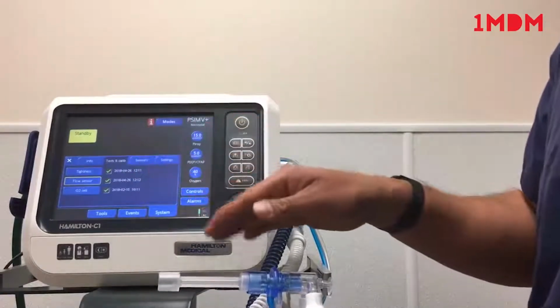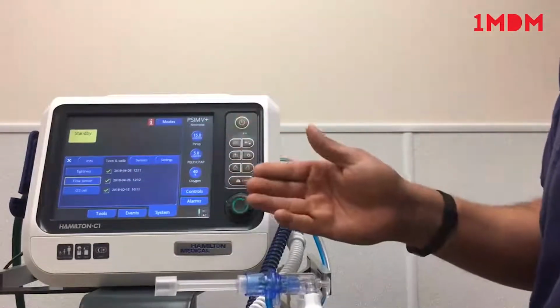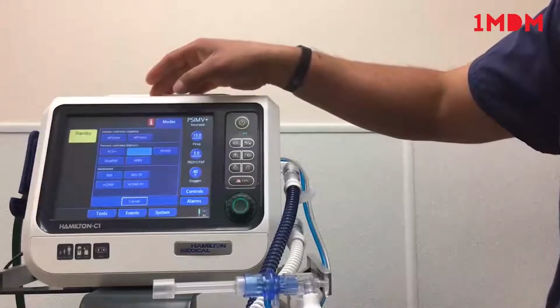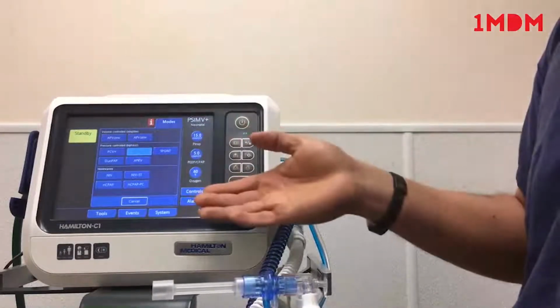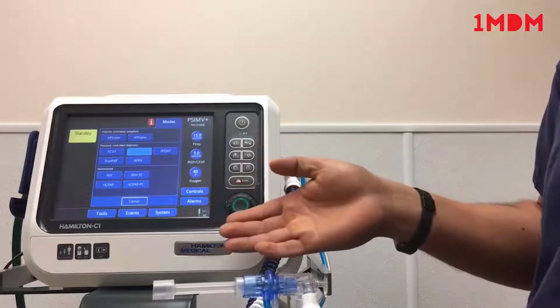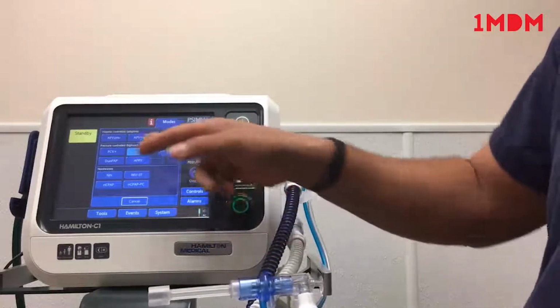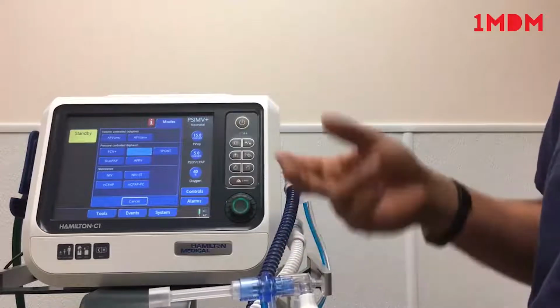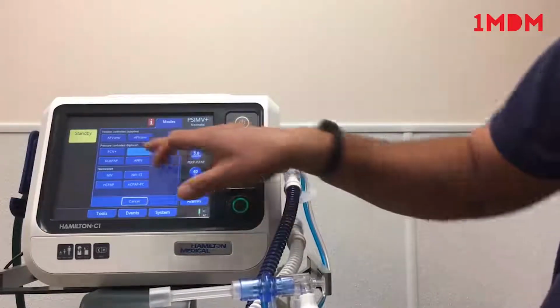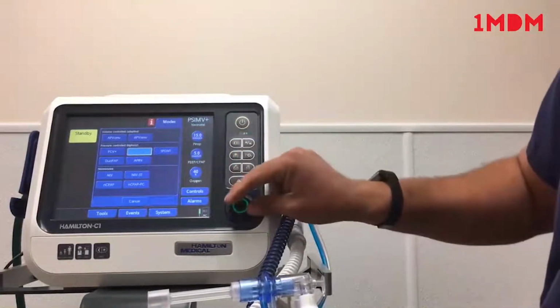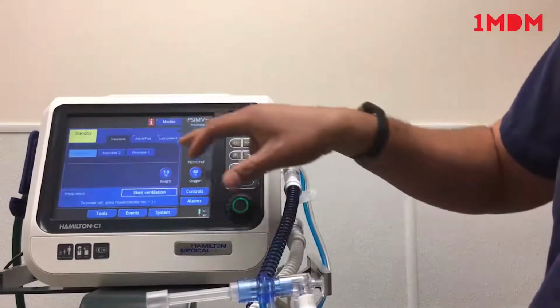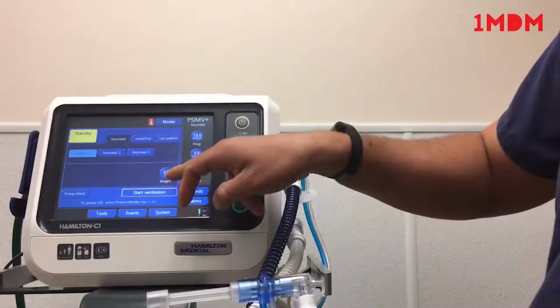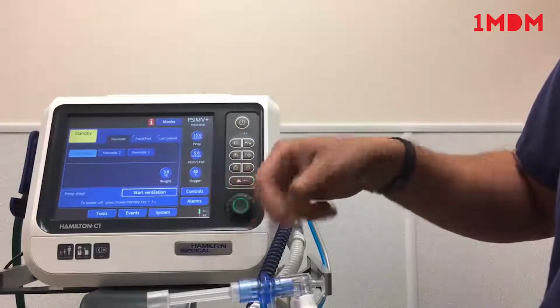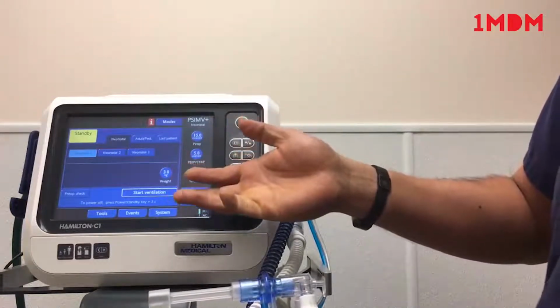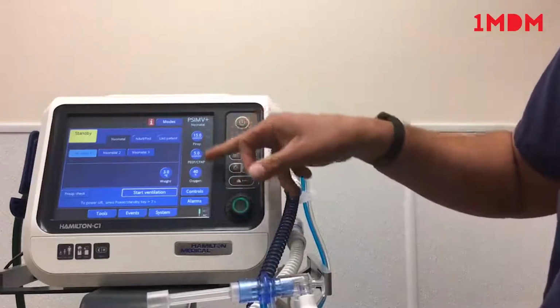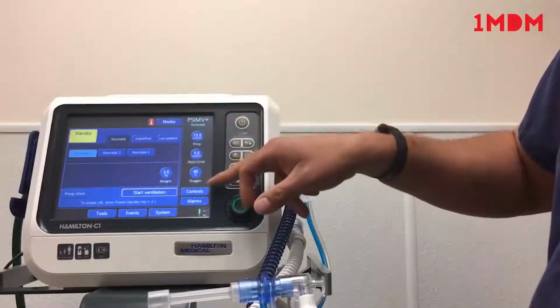We've done the tightness test. This means that your ventilator is ready to go. Now you go ahead and select modes of ventilation. If you're going to be doing invasive ventilation, meaning your patient is intubated, go ahead and hit PSIMV+. That's going to be really comfortable for your patient. Once you select that, confirm it, and you can exit the mode. And you can see here that you've selected 3 kilograms for a 7-pound newborn. That seems appropriate. Go ahead and set your controls appropriately.